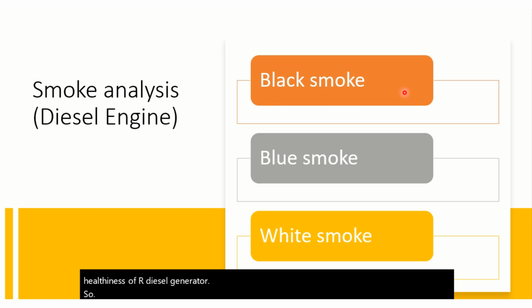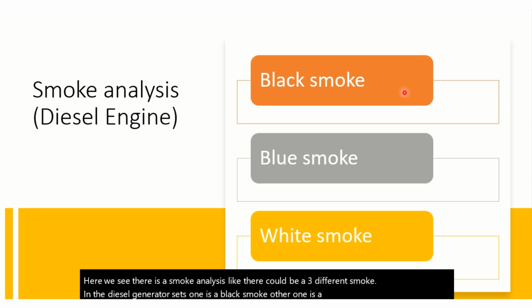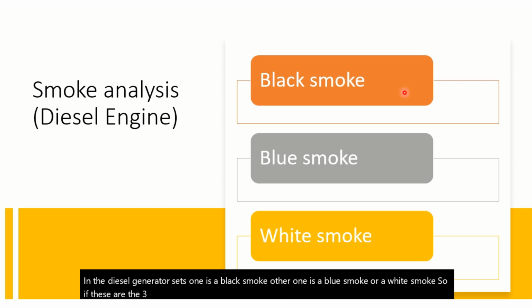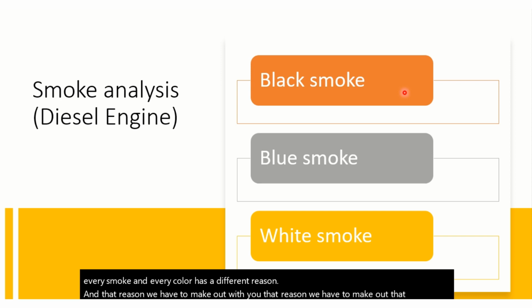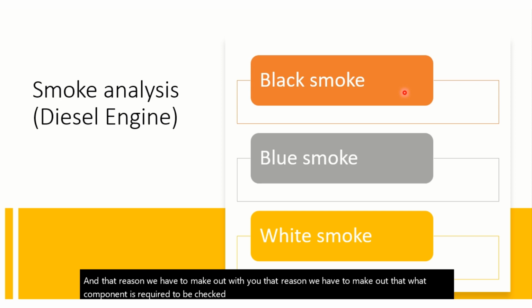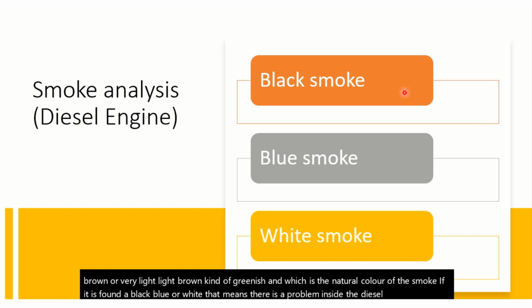Here we see the smoke analysis. There could be 3 different smoke colors in diesel generator sets: black smoke, blue smoke, or white smoke. Each color has a different reason, and through that reason we can make out which component has to be checked. The color of the smoke should be very light brown or light brownish-greenish, which is the natural color of the smoke. If it is black, blue or white, that means there is a problem inside the diesel engine which requires immediate attention.